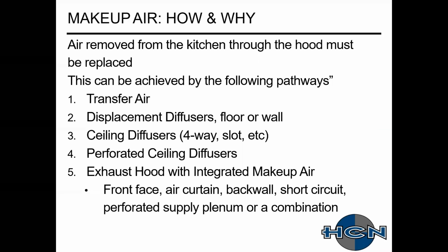So makeup air, how and why? Any air you're removing from that kitchen space is going to pull from somewhere. It's just physics. Like I said, it's a big vacuum, sucking up. We're going to have to provide air somehow. Different ways that we can provide it is through transfer air. That's a big one. It's been around for a while, but it's not really pushed as hard as it should be. Displacement diffusers, floor or wall, are very similar to transfer air. A lot of the testing labs actually test floor diffusers as the transfer air. You get great results with this.